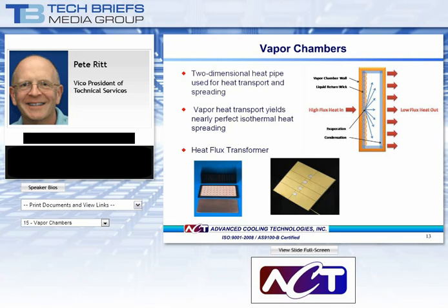They consist of a vapor chamber wick structure in the middle, a copper envelope seen below, and a heat sink seen at the top. Also pictured is a multiple evaporator, low CTE, coefficient of thermal expansion, high heat flux vapor chamber prepped for direct die attachment of 4 chips. As can be seen, vapor chambers can accommodate multiple evaporators.